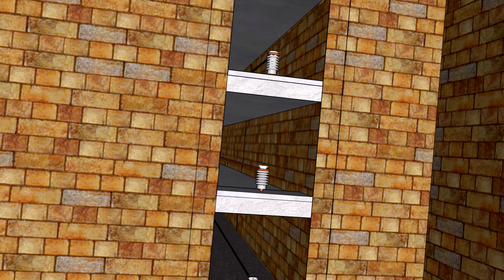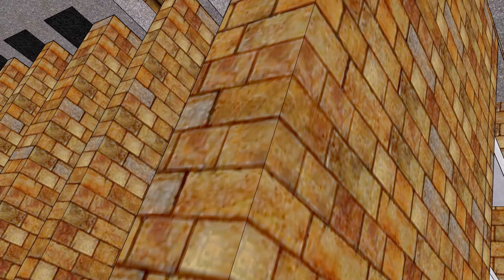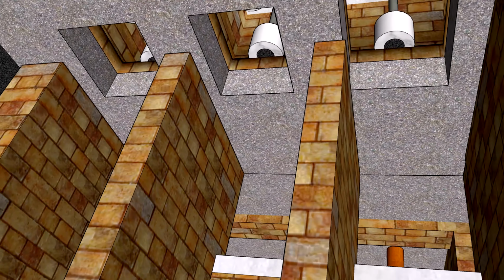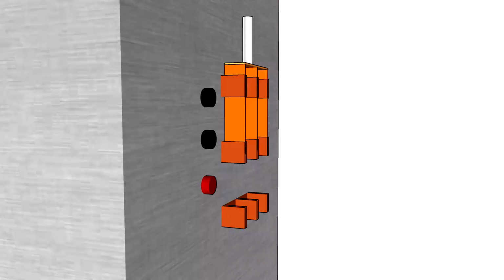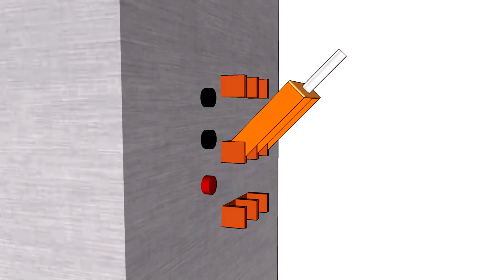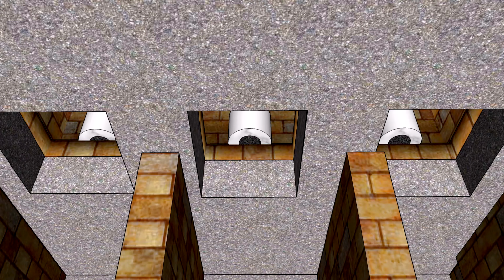The high-voltage AC connections to the bus bar were accomplished via motor-driven oil switches, which were housed in brick structures on the main floor, but connected via linkages to the bus bars in the basement. Throwing a manual jackknife switch on a high-voltage circuit would be extremely hazardous, not only for a human operator, but also for the switch itself, as the high potential of the AC current would almost certainly arc through the open air as the switch handle was folded down.